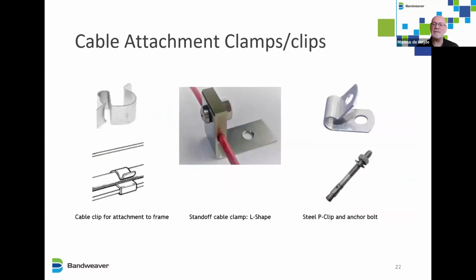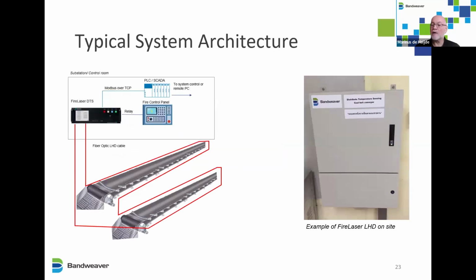A few examples of different clamps and clips, which you can find in any hardware store. It's just a matter of selecting the one that's most suitable for the frame you've got in place at your facility. There are clips, L-shaped clamps, steel P-clips, and various other types of hardware you can use. On the right-hand side of this slide, you can see a cabinet which has the unit inside it. On the left-hand side is a typical system architecture, where we can connect the DTS unit to a fire control panel via the relays, as we showed in the video.